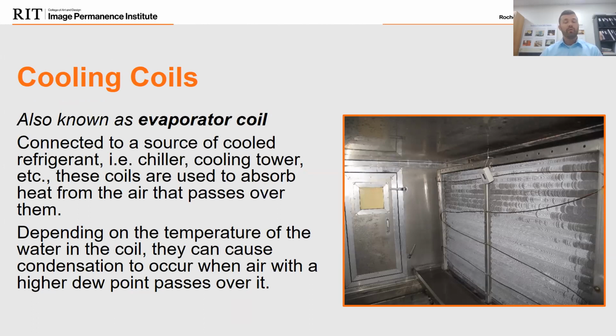When you talk cooling coil with anyone in facilities or HVAC systems, a cooling coil does not add cold to the air. We never add cold. We remove heat from the air. So it's one of those important terminologies that you want to think about. We're not adding cold, we're removing that heat from the air. Depending on the temperature of the water in that coil, this can cause condensation to occur, and that's going to help us reduce that dew point. As previously shown on the previous slide, we were aiming for a 50-degree dew point, and the air that's going to be coming across is a 57.